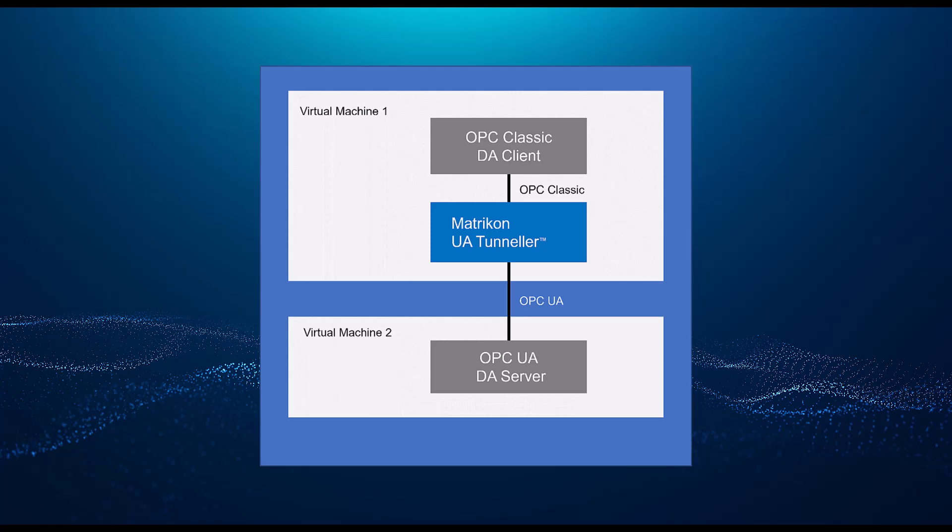For those that aren't aware, OPC UA can support real-time data transfer known as DA, historical data transfer, which is now known as historical access or HA for short, and alarms and conditions or AC for short. These should not be confused with the classic OPC DA, HDA, and A&E. An OPC UA server can support one or many of these, but is not required to support all. So it is important to check with your vendor which features your OPC UA product support.